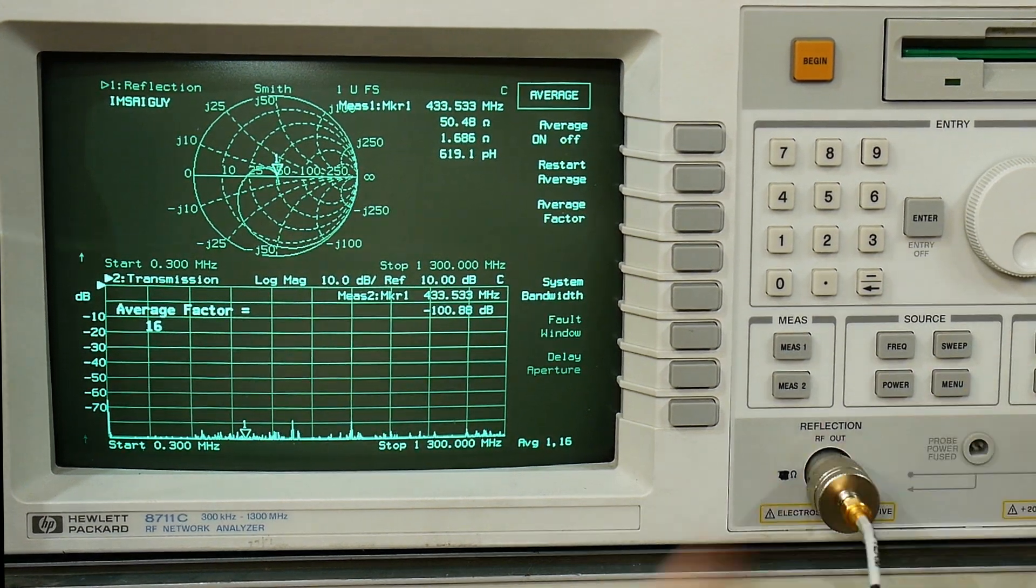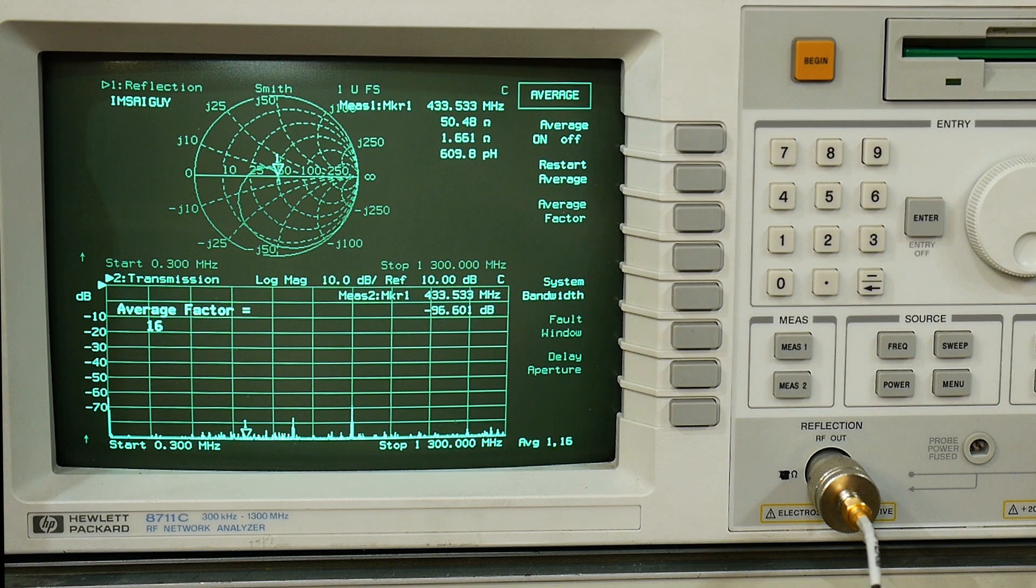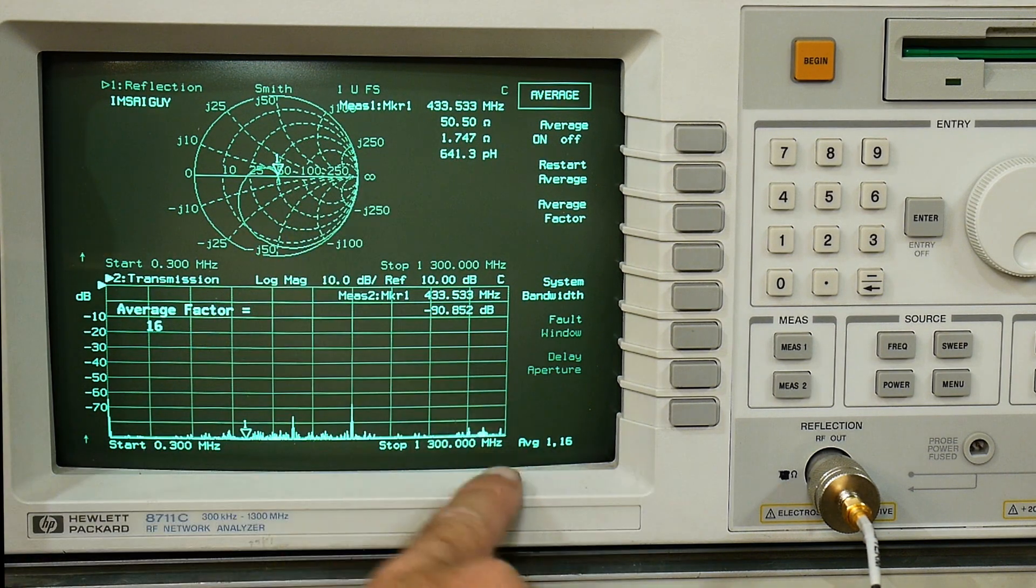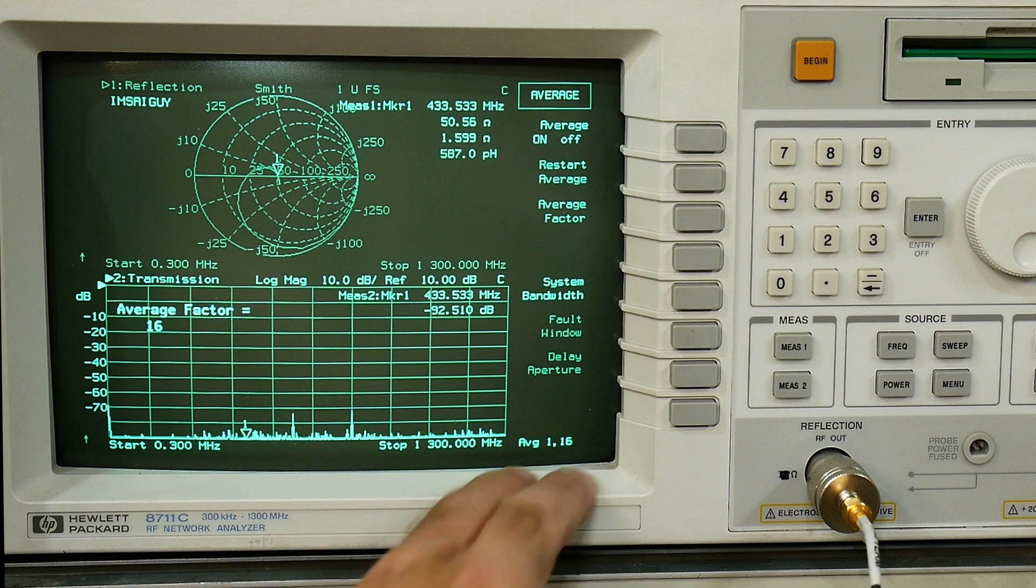Oh yeah it's in averaging. So you can set averaging. You can set the averaging factor and down here is displayed the averaging factor for measurement one and the averaging factor for measurement two. So measurement two is having an average of 16 so it's averaging 16 sweeps.